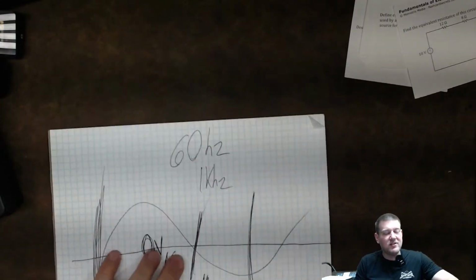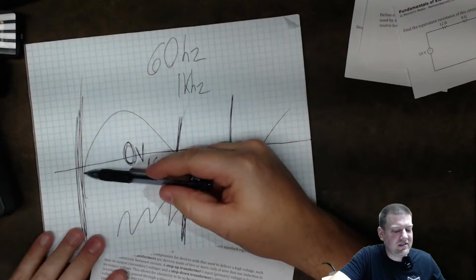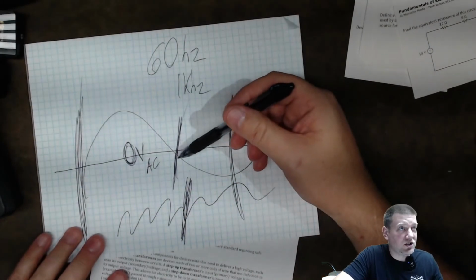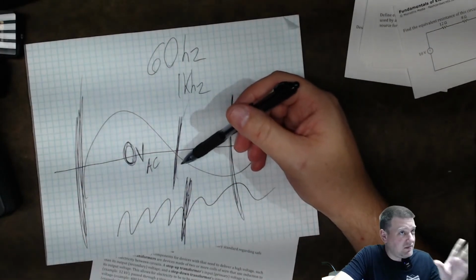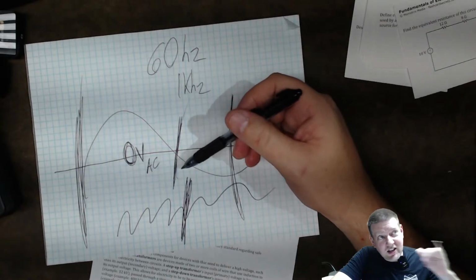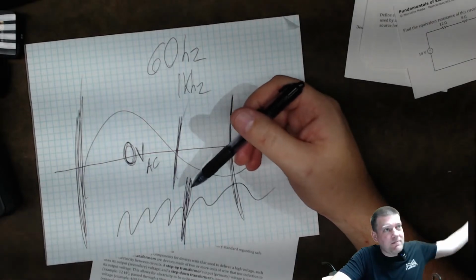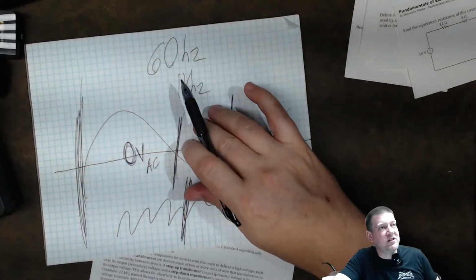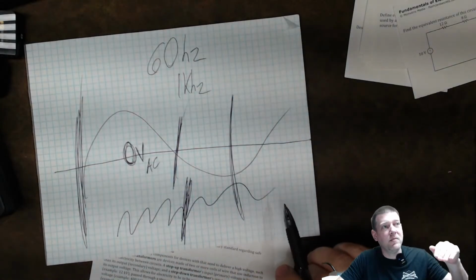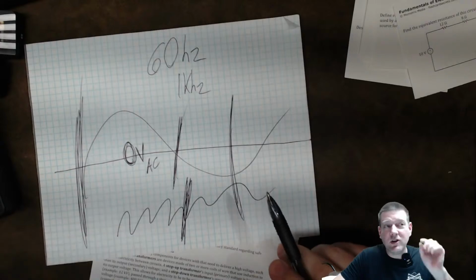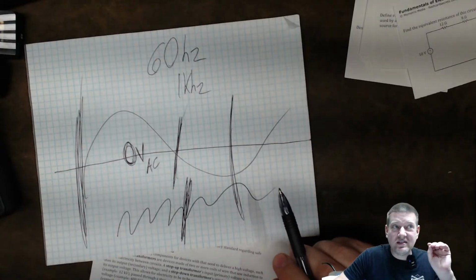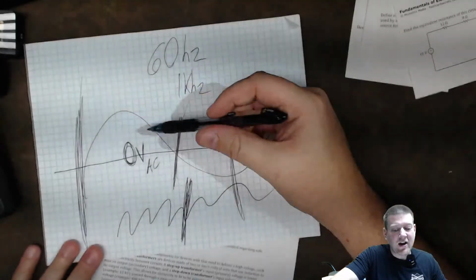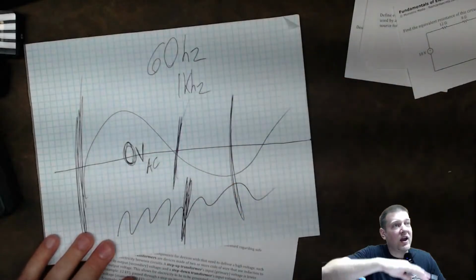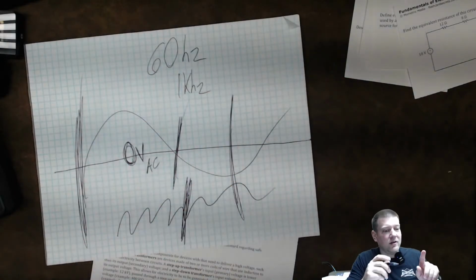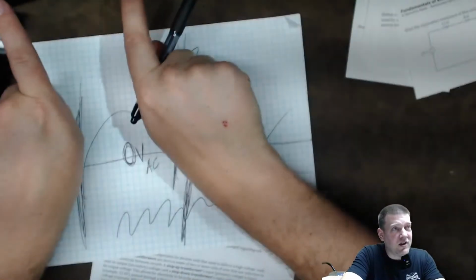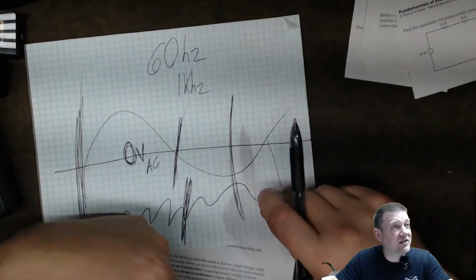So UPS systems, all they do is sense when the current is no longer changing directions, because remember it's 60 times a second. When it's not changing that direction, it says, hey, switch. And it switches over because it loses that difference of potential. When it starts switching over, you can hear those little SCRs buzzing - what they're doing is switching on and off, creating a waveform, sending some current this direction and some that direction.